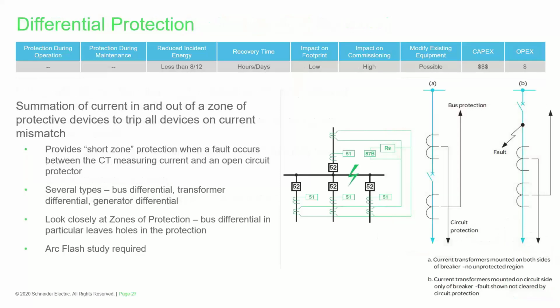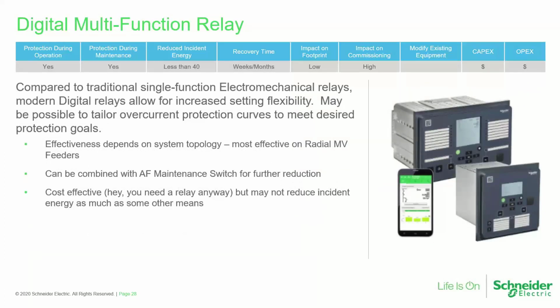Differential protection. I'm going to skip past that one to get to a couple more here and leave us some time. Digital multifunction relays. This is an example of one where it's a relatively low incremental cost, right? If you're laying out a medium voltage system, you're going to have protective relays in there of some sort, or at least if you're using circuit breaker protection. And so make sure that you're specifying relays that give you enough flexibility in order to get those levels down where you want them to go.